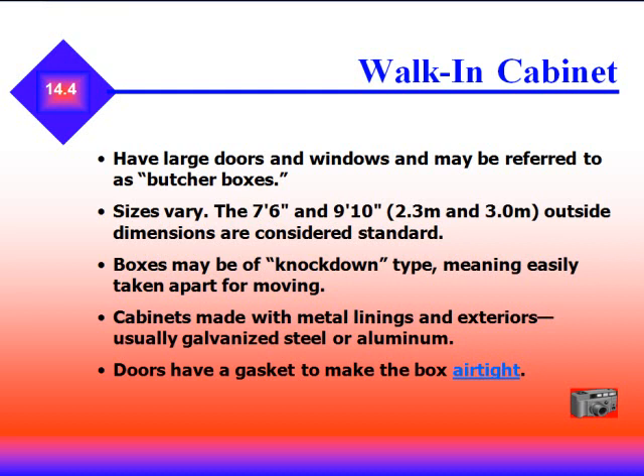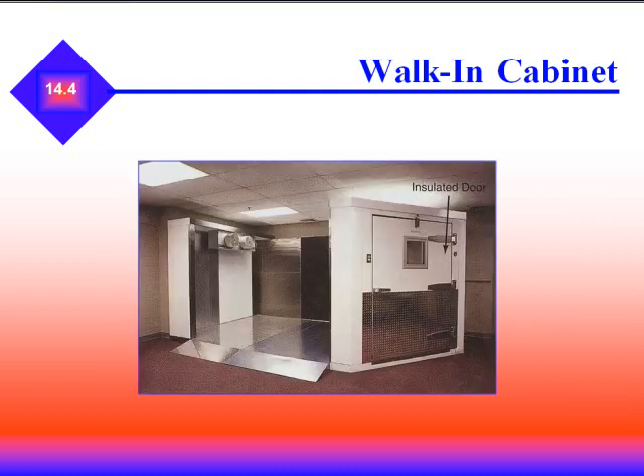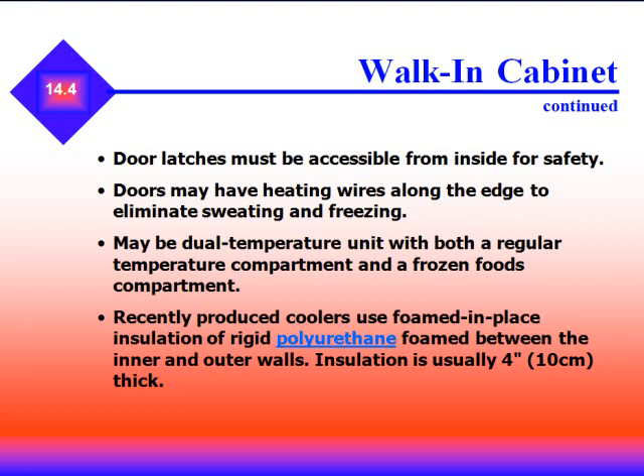Walk-in cabinets have large doors and windows and may be referred to as butcher boxes. Standard outside dimensions are 7 feet 6 inches and 9 feet 10 inches. Boxes may be of a knock-down type, meaning easily taken apart for moving. Cabinets are made with metal linings and exteriors — usually galvanized steel or aluminum — and all doors have gaskets to make the box airtight. Door latches must be accessible from the inside for safety; this is the law. You must be able to get out of the box even if someone blocks it. Doors may have heating wires along the edge to eliminate sweating and freezing.